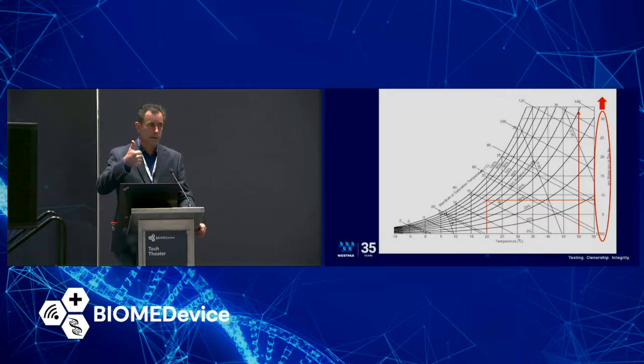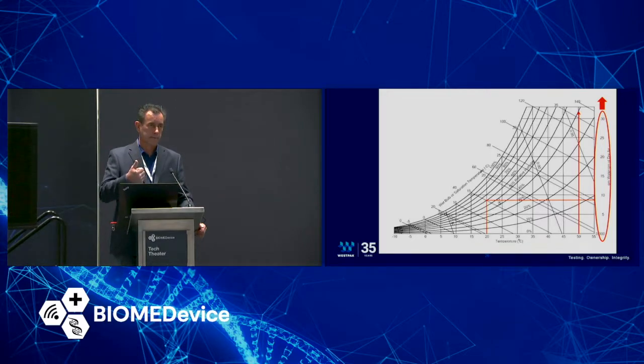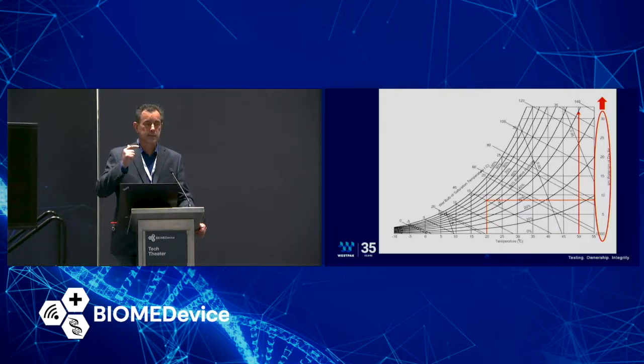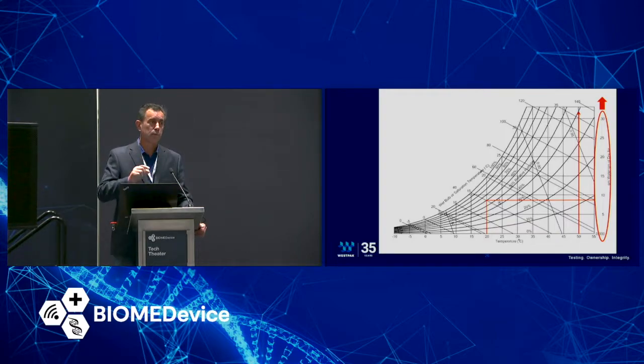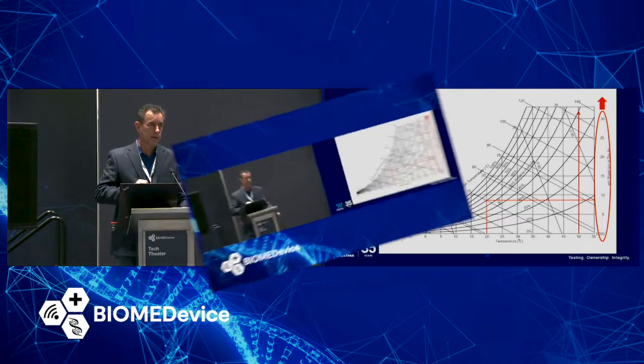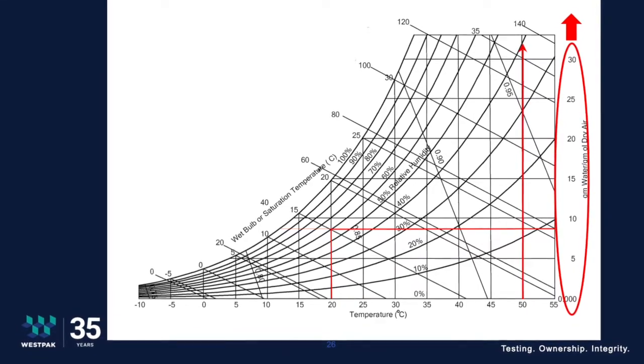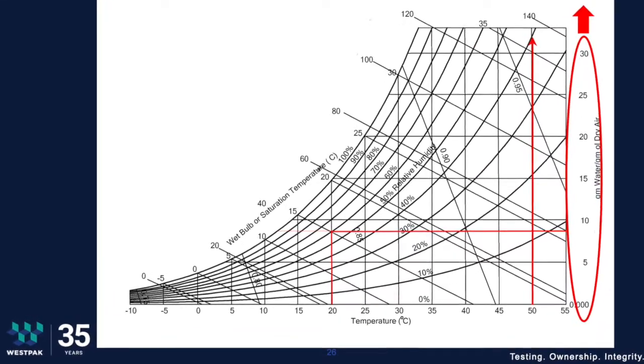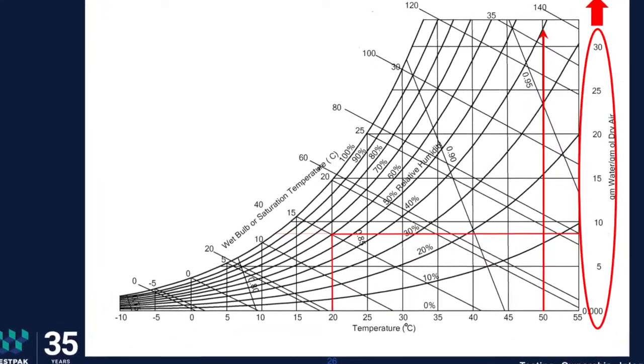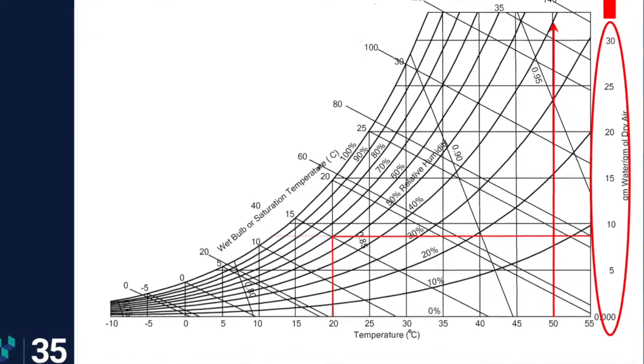The point is: first, look at the scope of your testing for accelerated aging — are you looking at the packaging or the product? Second, if you have a product that has sensitivity to humidity, meaning sensitivity to low humidity, determine what is an acceptable humidity before you introduce humidity into your accelerated aging program. It's the total moisture content in the chamber that we're concerned with, not relative humidity.